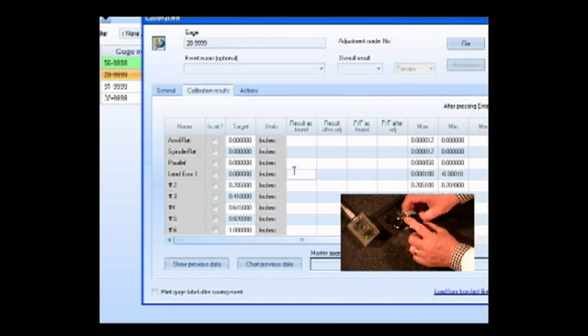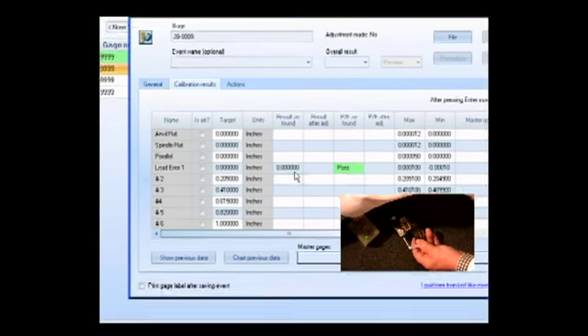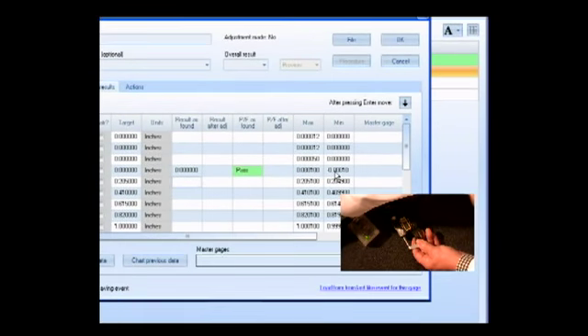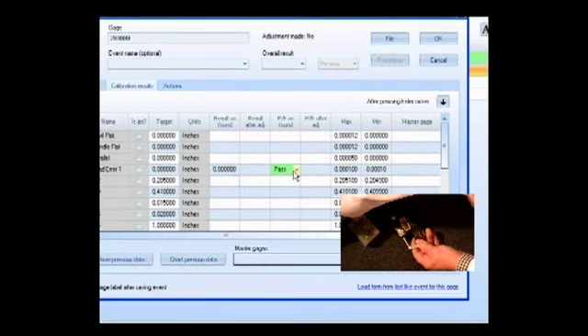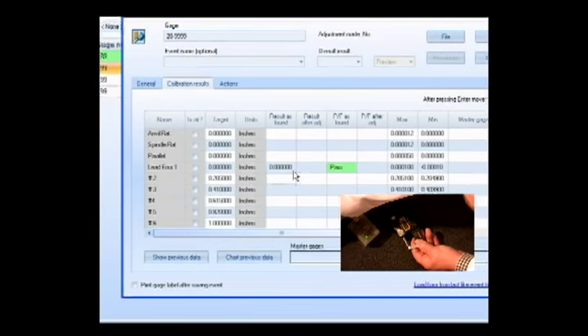True. And this has a little button here. When I push the button, it's going to take the reading and plug it right into the software. So our first measurement was done with the gauge closed, and we're going to immediately push the button. It immediately inserts it right into the software. It shows the reading. It compares it with the known tolerance that's already been established. It issues a pass for that feature.